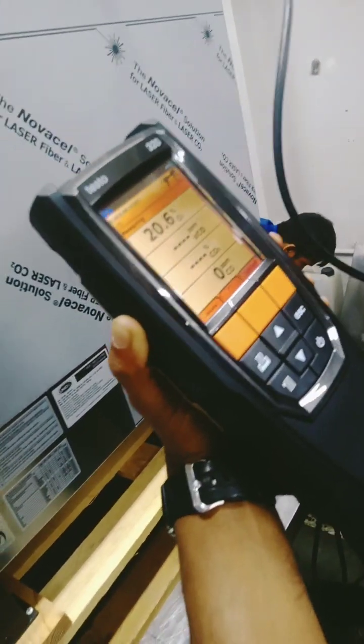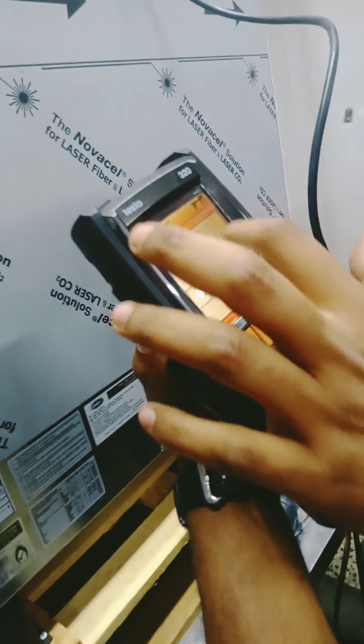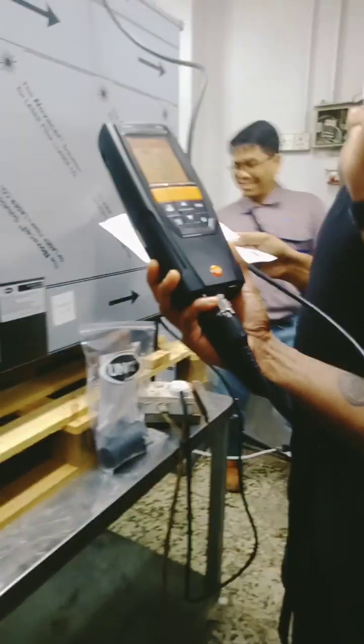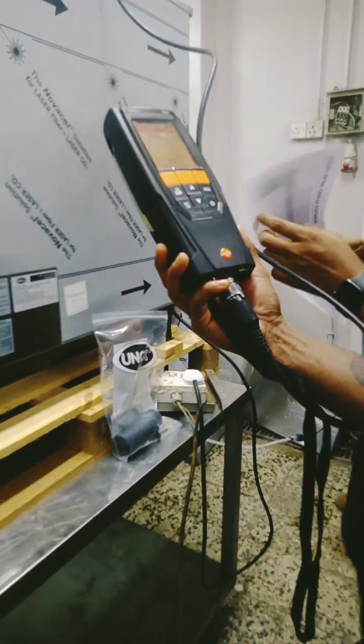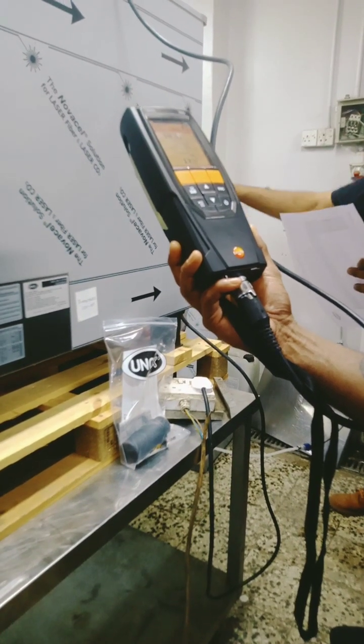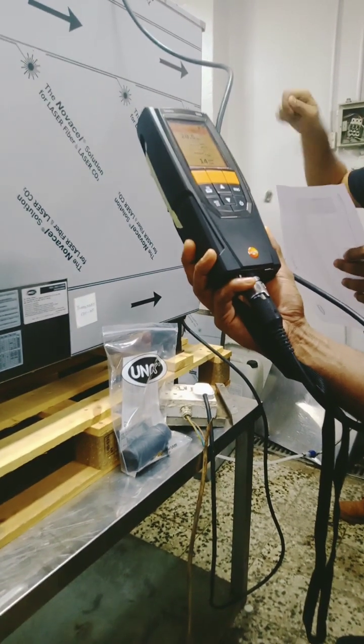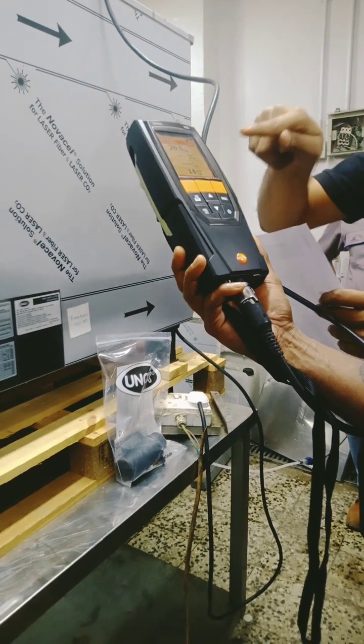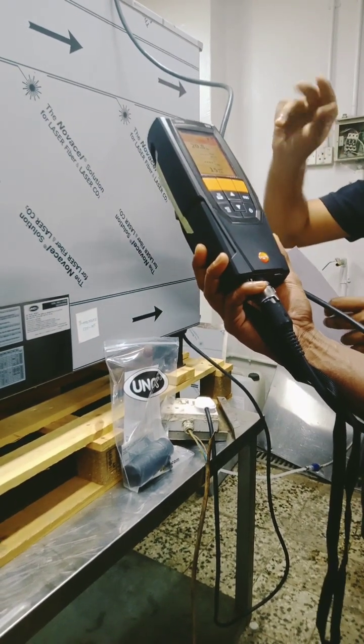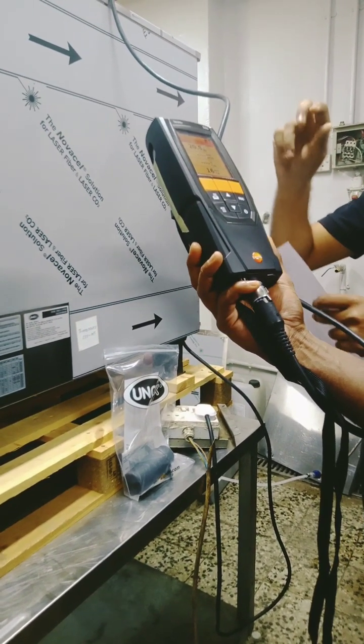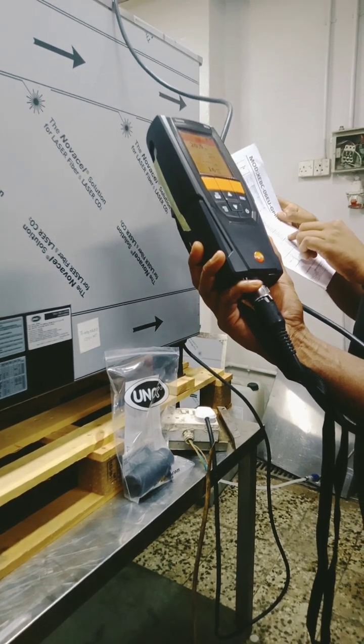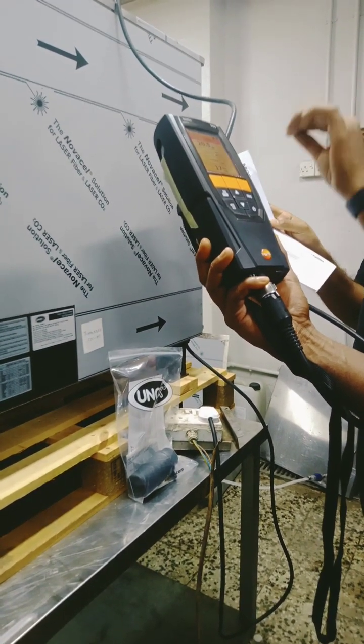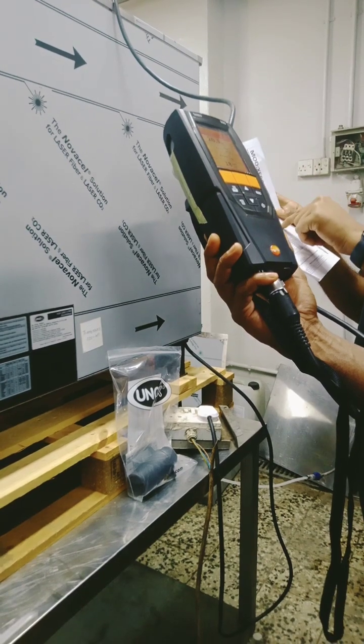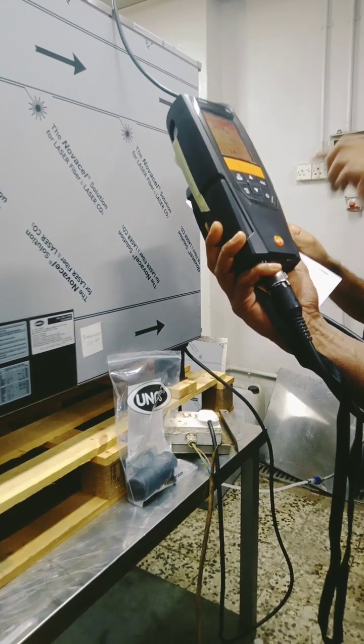Not this one, not CO2. These two values. It's not working. Yeah, the sensor is not working. Maybe it's 10.5, for example. Then I'll adjust this throttle slowly, clockwise or anti-clockwise. If I rotate anti-clockwise, I'll check whether it's increasing or decreasing. If it's increasing, I'll rotate more slowly until it reaches between 11.8 and 12.5, and CO less than 30.